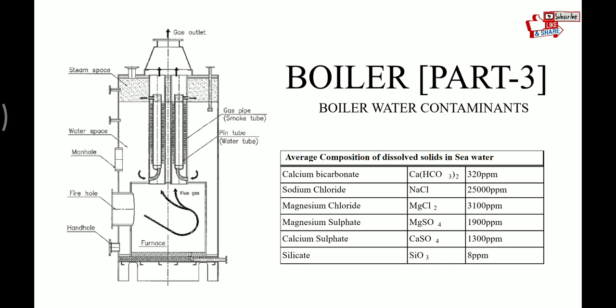Boiler water mostly gets contaminated by seawater. Let's see the average composition of dissolved solids in seawater. First is calcium bicarbonate at 320 ppm, sodium chloride at 25,000 ppm, magnesium chloride at 3,100 ppm, magnesium sulphate at 1,900 ppm, calcium sulphate at 1,300 ppm, and silicate at 8 ppm. These values are approximate values.